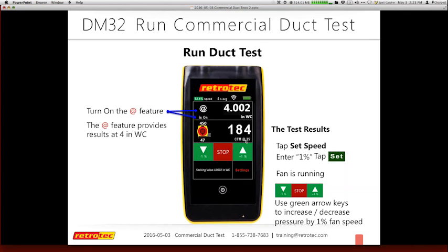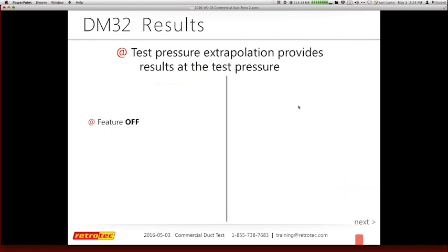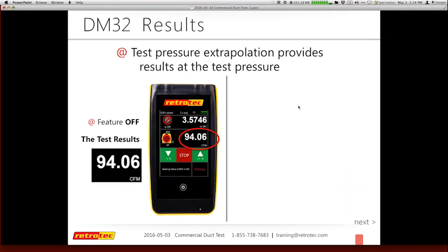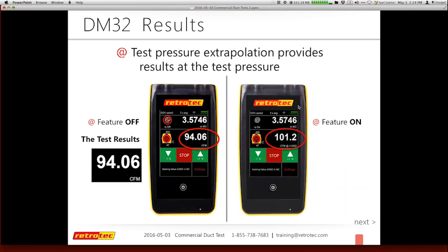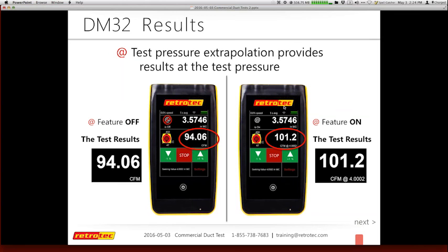So this not only gets rid of that problem, but also does the flow measurement mathematically at exactly 4.0000 inches. So it actually does the math for you on an ongoing basis. What you're reading is the gauge doing the math for you on a constant basis, so that the gauge, I guess, reading error goes away, because every time you look at a gauge, one minute it's 3.9, it's 3.95, it's 4.05, etc. It's hard to get a gauge to read exactly 4.000. This does the math to give you the result at exactly 4.000. So that's the first point, which this more or less shows.